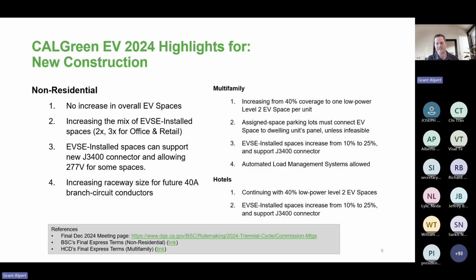If there are parking lots not connected to the actual building — say in a condo complex with assigned spaces — the EV space has to connect directly to the breaker panel. This allows for easier billing for multifamily units, with some exceptions if it's an infeasible ask.